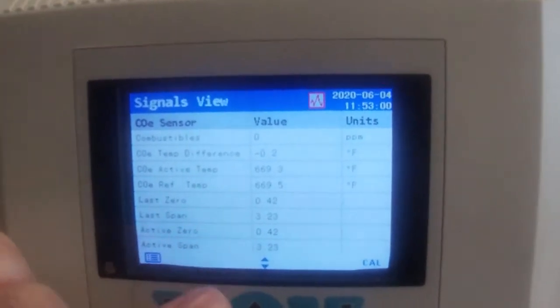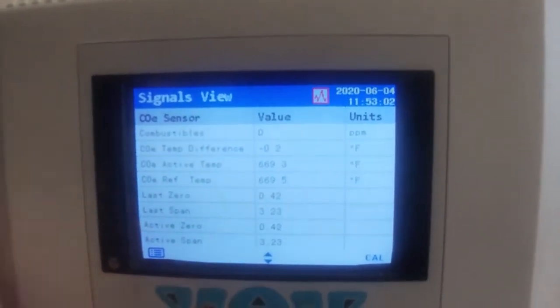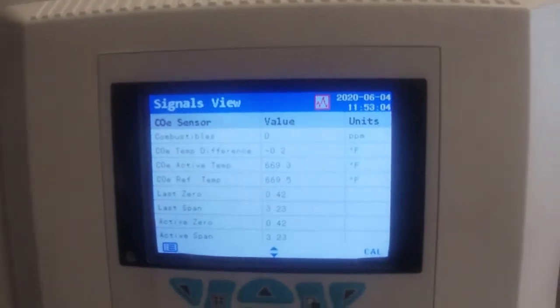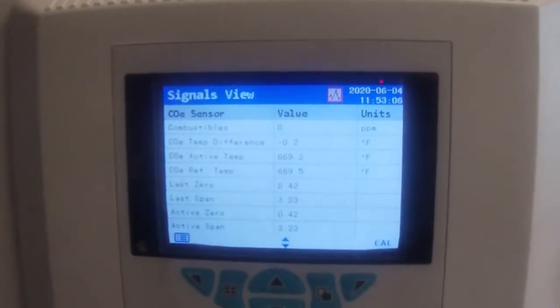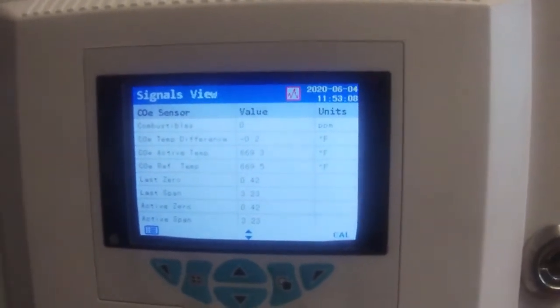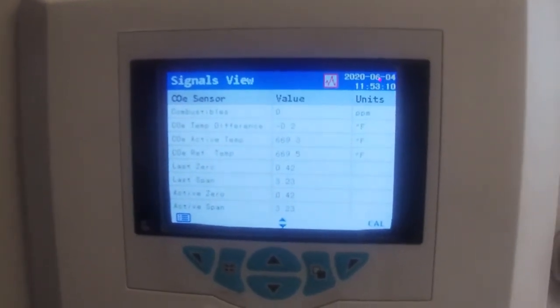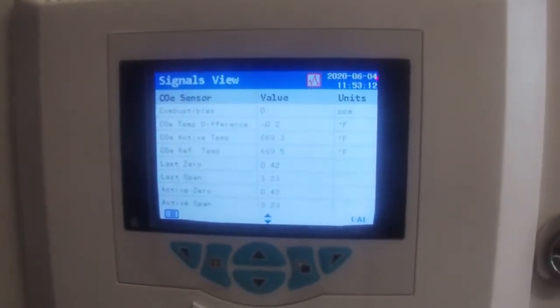Again, last zero and last span, active zero and active span, and if it's currently calibrated, those are exactly the same. But if I tried to do a calibration and ran out of gas, they would be different numbers, and later on it's going to let me restore the old values.